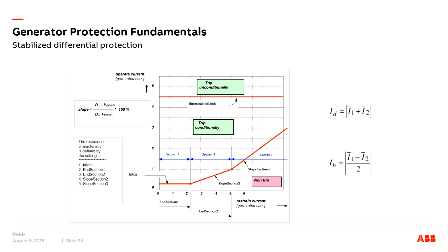Now let's take a look at the differential protection characteristic. In the electromechanical relays, we had only the possibility of a single slope characteristic, but with the modern microprocessor relays, we have the possibility of creating a multi-slope characteristic. And how is it beneficial? So here you have the multi-slope characteristic, which has 3 sections, and the bottom portion of it is a non-trip area, and here is a trip area which is a conditional trip, and above this limit is the unconditional or unrestrained operation of the protection. And here this is the plot between the operate current, which is the differential current, and the restrained current or the bias current.